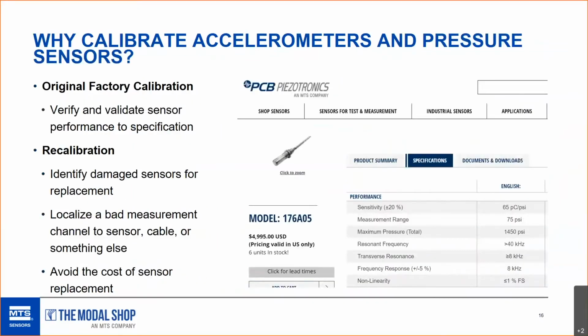So, what do we do when we calibrate accelerometers and pressure sensors? There are two sets of two calibration events in the life of a sensor. The original calibration of the sensor: the purpose of it is to make sure that PCB meets the promise it makes on PCB.com, where there's a combustion dynamics pressure sensor, and PCB specifies its characteristics in the lower right-hand corner. PCB makes that commitment on a product specification sheet, and what we do in final calibration is make sure the sensor conforms to that. It's a 100% acceptance test at the end of the line.